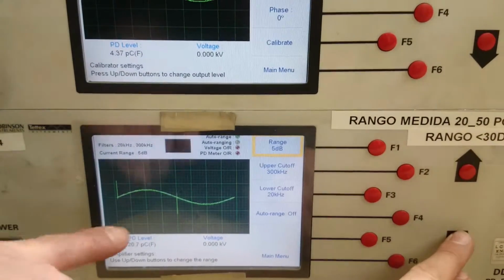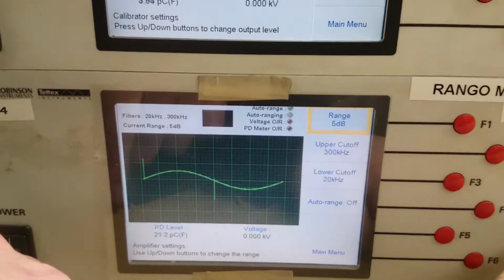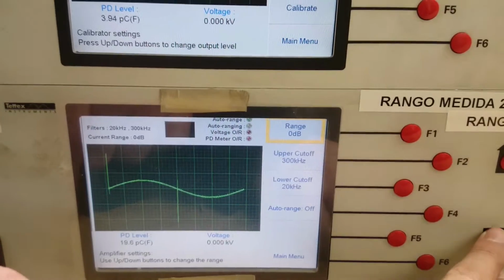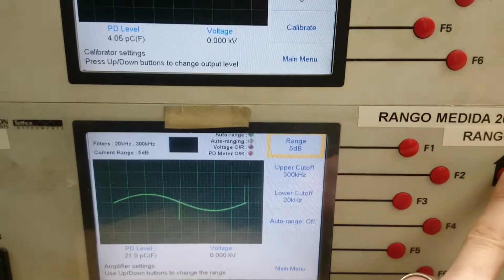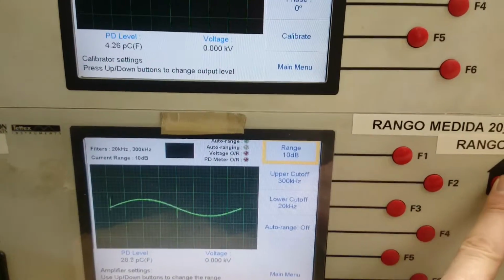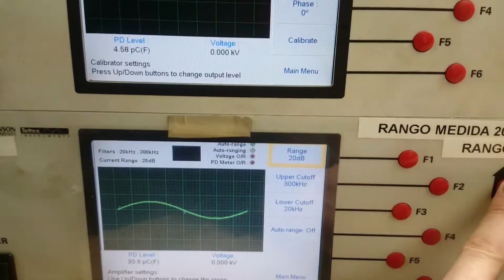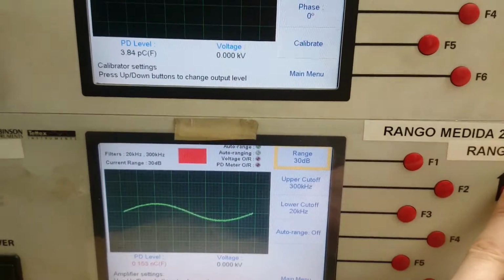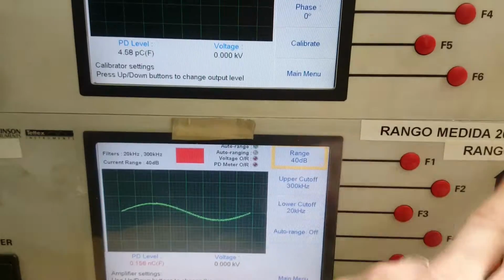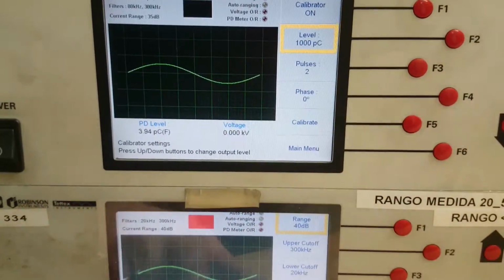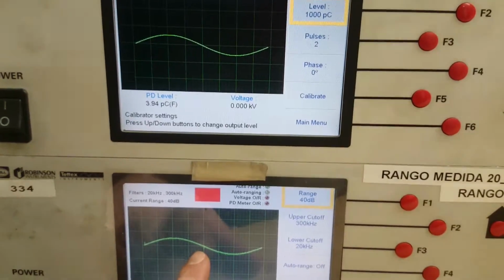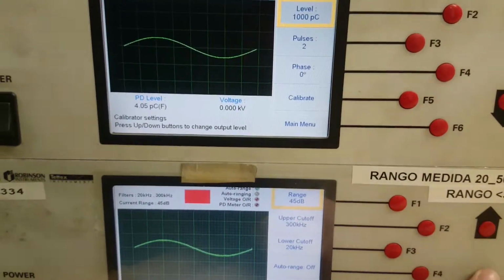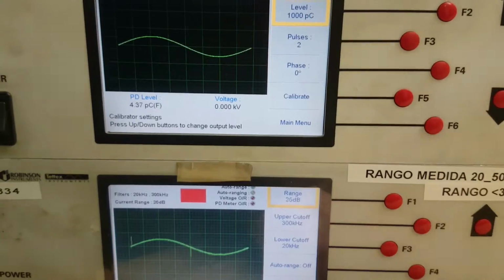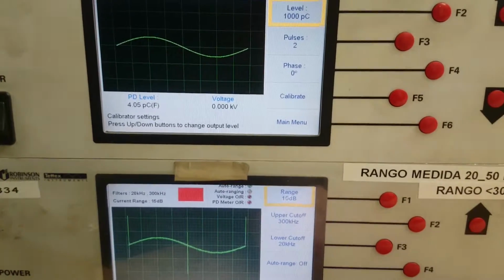So if we look at the pulses, we're going to go bigger, and they go bigger, and if I go the other way, they're going to get smaller, smaller, smaller, smaller, until they disappear. Just make sure they come back when I increase the signal. And you see they're just very small coming back there. Smaller again. Bigger, bigger, bigger, bigger. So that's all working, the ranges are working.